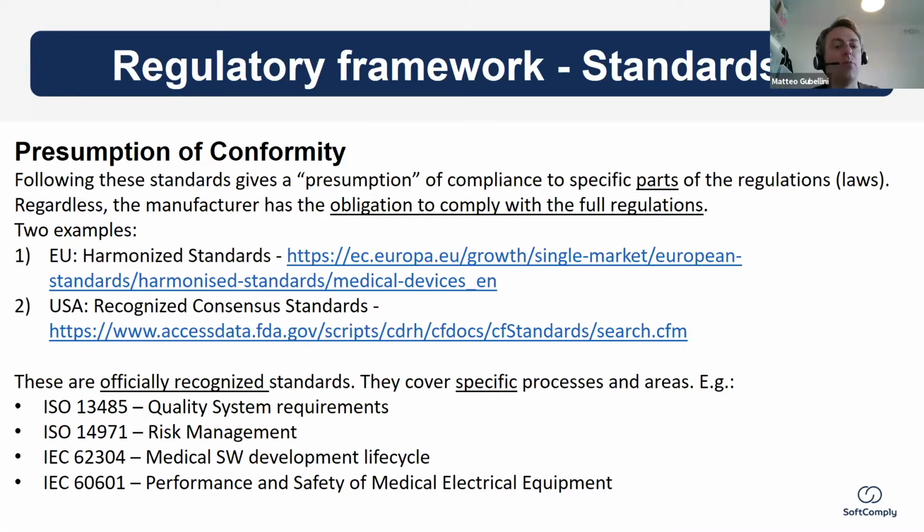Okay, so it doesn't cover everything. It doesn't mean that if you comply to 13485, you're automatically compliant to everything that is in the MDR or 21 CFR, the Code of Federal Regulations, but it covers part of that. It is important to note, as I said, you have the obligation to comply with the full regulations.